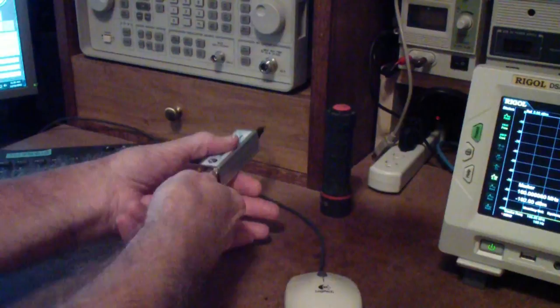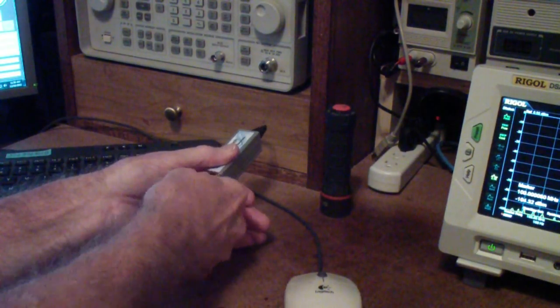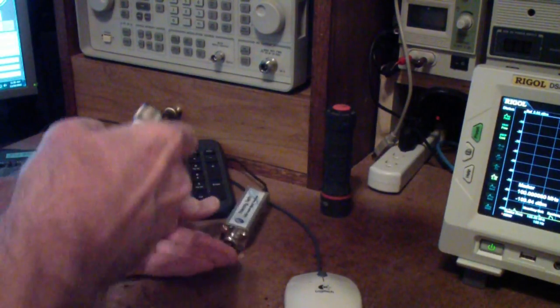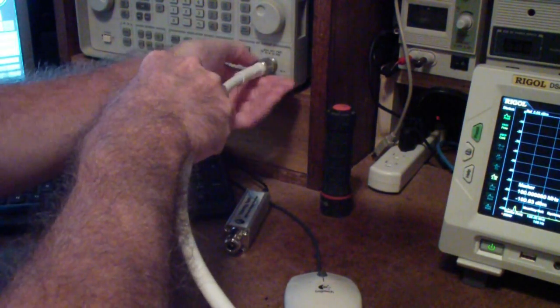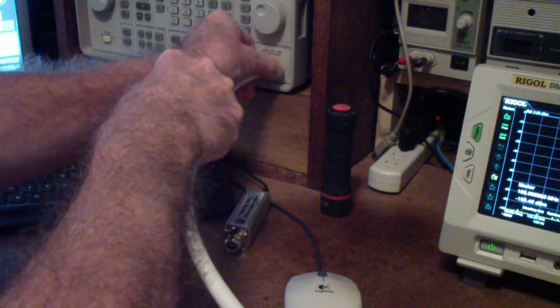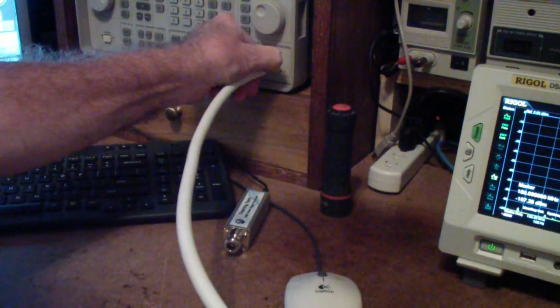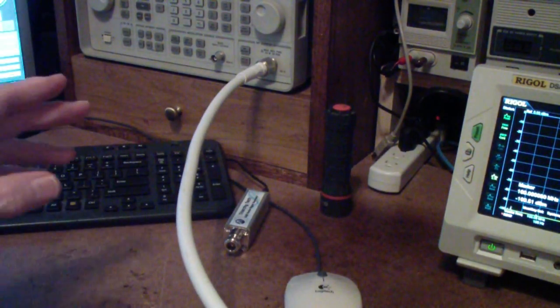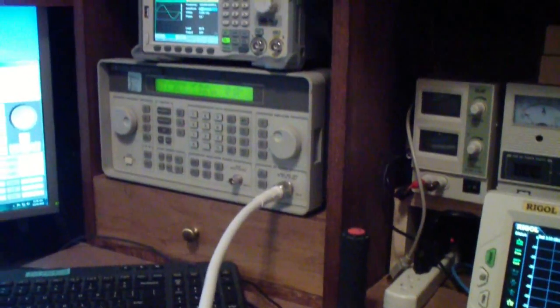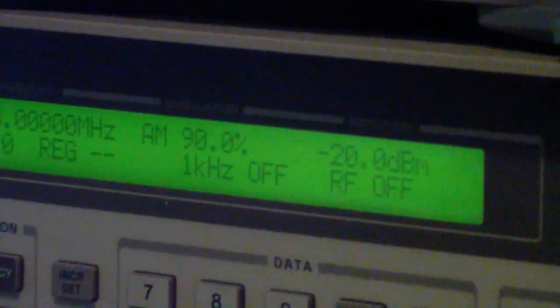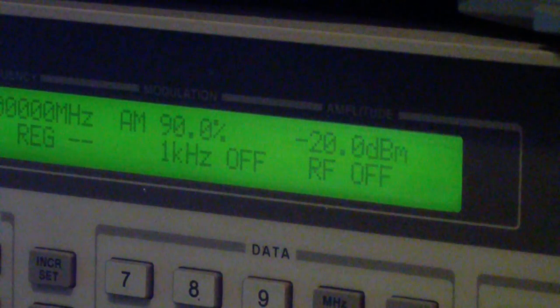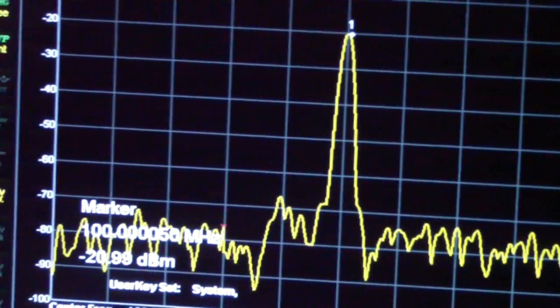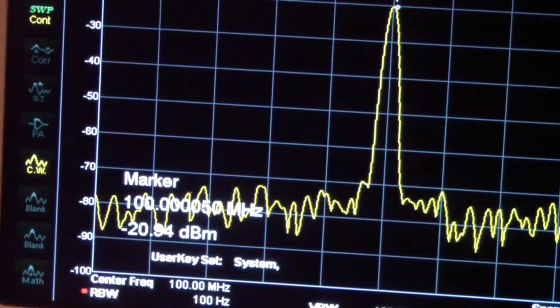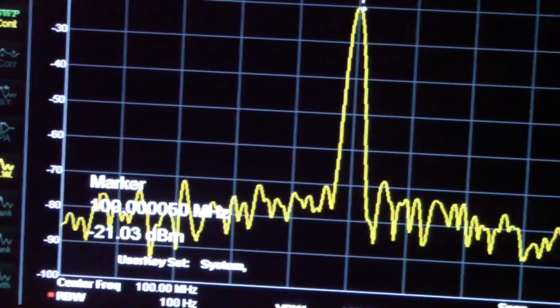I thought I would just show you the operation. I'm going to be disconnecting the end connector from the Triarchy and connecting it now to the Hewlett-Packard, which I have previously found this generator to be pretty accurate. But at any rate, it's now connected there. Now, as you recall, I'm using about minus 20 dBm, and the RF is off. Let me now turn the RF on. And now let's go look at the Rigol, and as you see, it says the marker is at 100 megahertz and that it's minus 20 or 21 dBm.